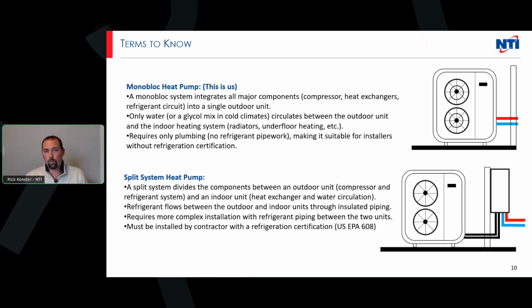So if you've got really cold refrigerant on one side and water on the other, and you put in no glycol, there would be some opportunity where, if that refrigerant got too cold, you could freeze the water in a flat plate heat exchanger, and that could do some damage as well. So those are your two different types.